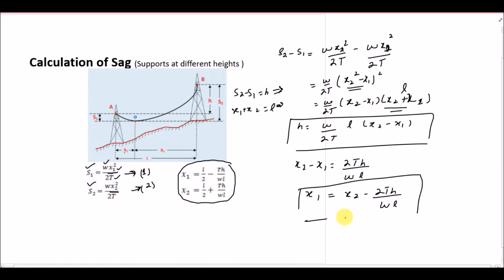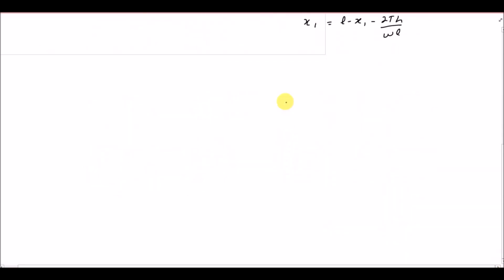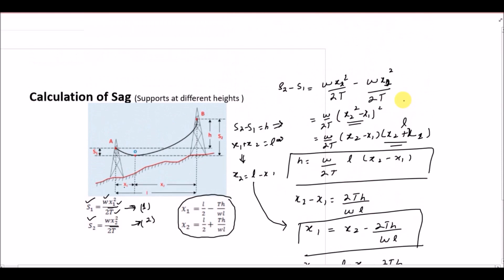We know that x2 = L − x1, so substituting into the equation for x1: x1 = (L − x1) − 2Th over WL. After solving, 2x1 = L − 2TH over WL, giving x1 = L/2 − TH over WL. Here x1 is the distance from the lowest point of the conductor to the support point at tower A.